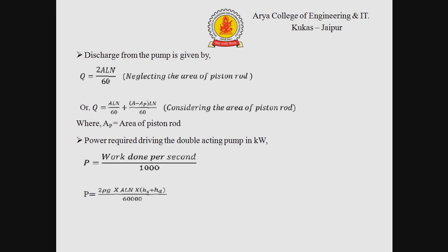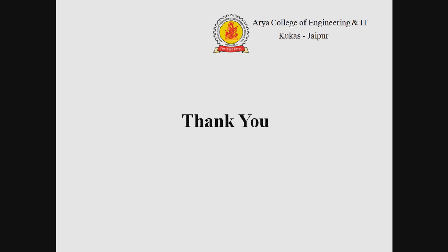The discharge from a double acting pump is given by Q = 2ALN / 60 when neglecting the area of the piston rod. If we consider the piston rod area, then Q = ALN / 60 + (A - AP) × LN / 60, where AP is the area of the piston rod. The power required to drive the double acting pump in kW = 2ρgALN(HS + HD) / 60,000.